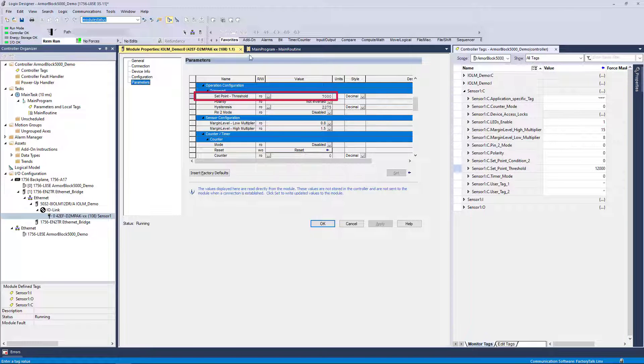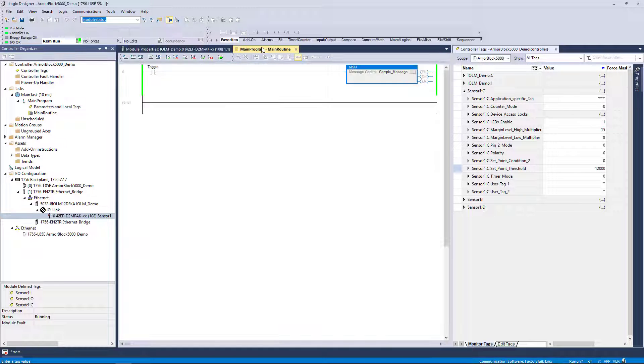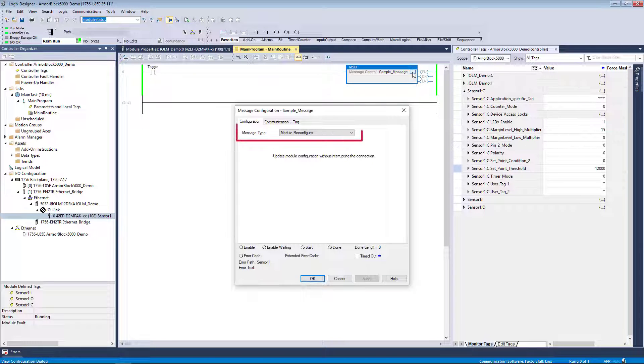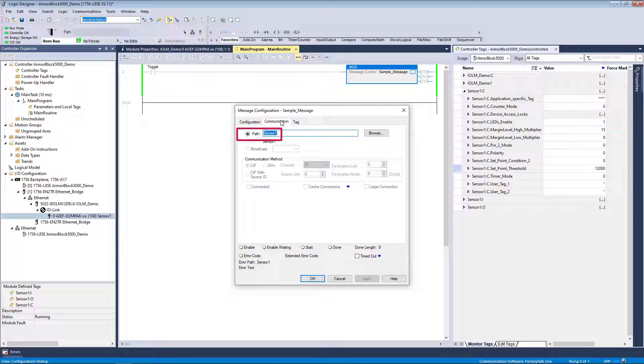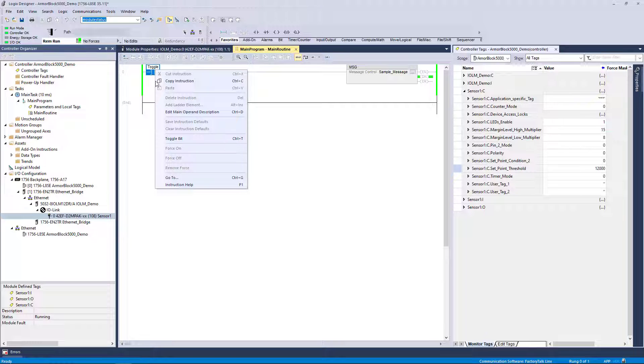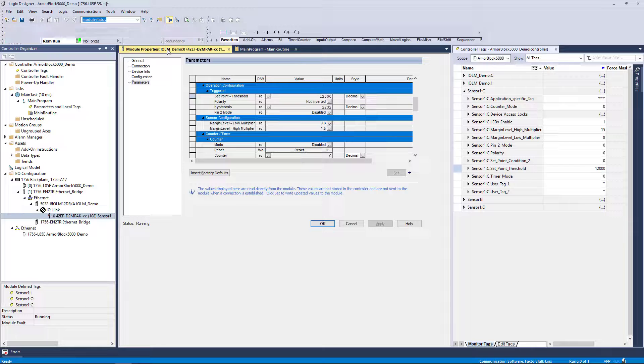Instead of correlating via the add-on profile, we will show how this change can be pushed to the IO-Link device through logic instead. To make the update in the IO-Link device after a tag-driven configuration change, we can use a module reconfigure type message instruction. Observe that the target of the message is the IO-Link device itself. Let's trigger the rung with the toggle of a bit. Finally, we can observe that the value is updated to 12000 on the Parameters tab following the message execution.